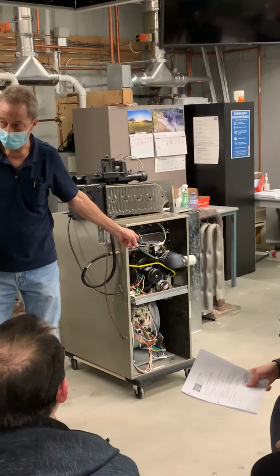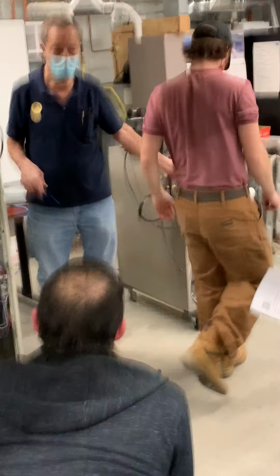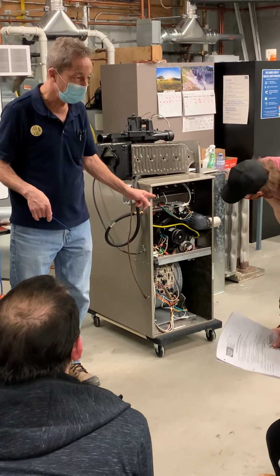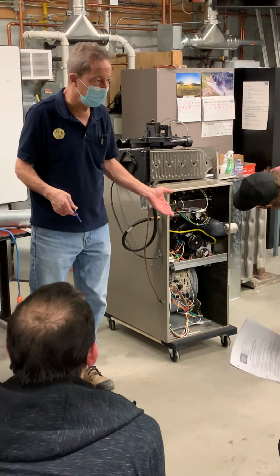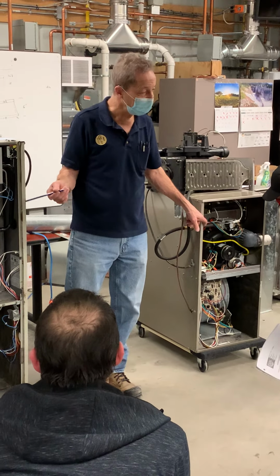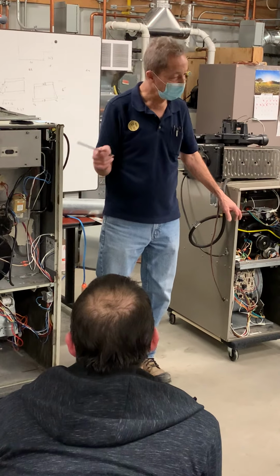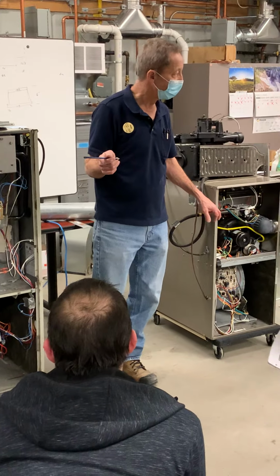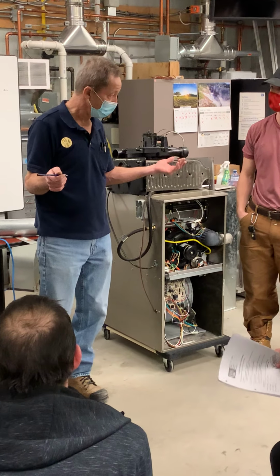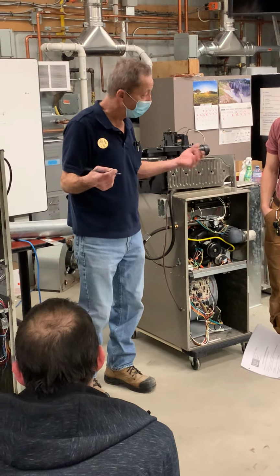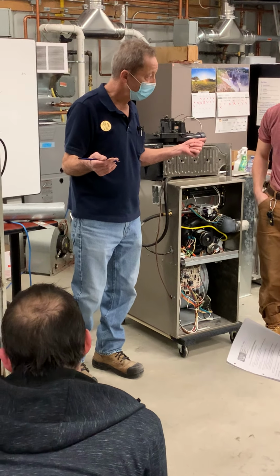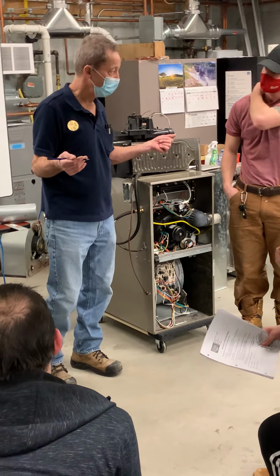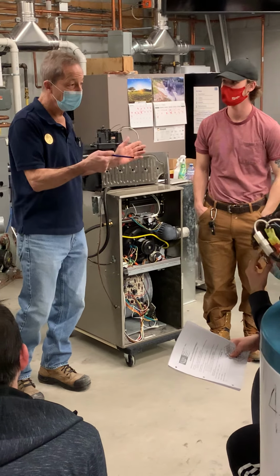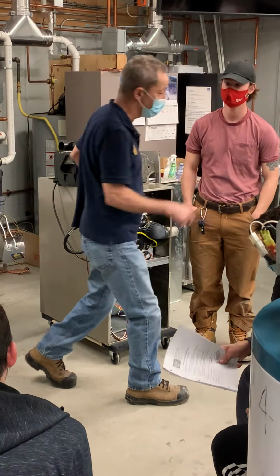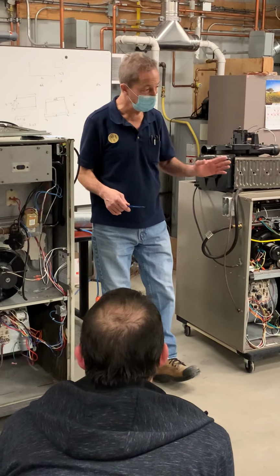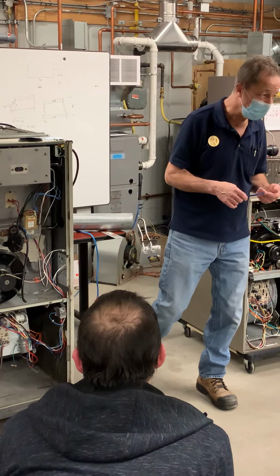Look at this one. Does it have it over here? The hose, you mean? Yeah. No. From the gas valve. No, it doesn't. This one does have a hose from the gas valve to the sealed burner box. Why does it have that? Because it's a sealed burner box. Keep going. Why do I need that hose? I'm not sure. Not as much gas flow in there? So there's not as much gas flow? Exactly. And why would there possibly be too much gas? Because it's sealed. Go on.